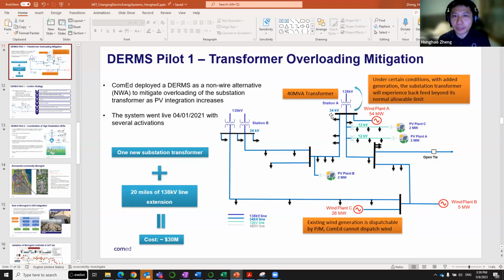Yep, that's a really good question. First, I'd like to emphasize this is on the 34 kV network, not the 12 kV that we usually have on the distribution side. The relay protection settings have been specifically adjusted for this system because they noticed there's a lot of heavy wind farms in the area, and they need to prepare for this backfeed into the system. So yes, our relay protection team has been doing the settings and studies, because this is almost like the normal hours now, they're always having this backfeed since the wind plant is always generating.